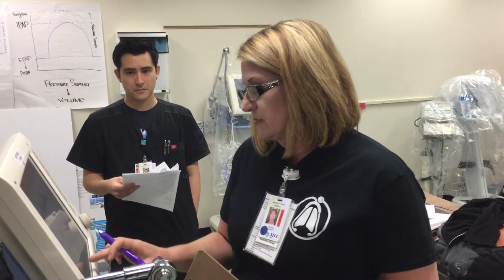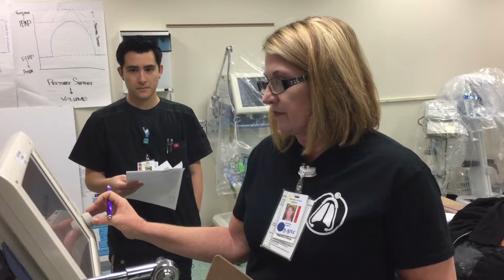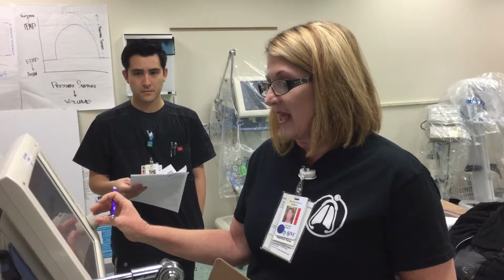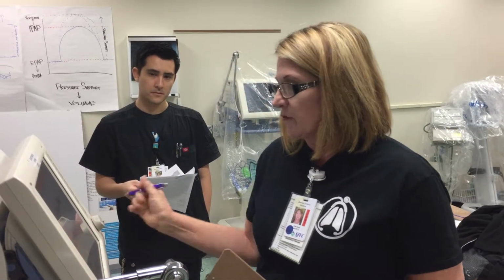I'm going to set her inspiratory time at 1, frequency at 15, her max pressure at 30, her flow at 40, and her PEEP at 5.